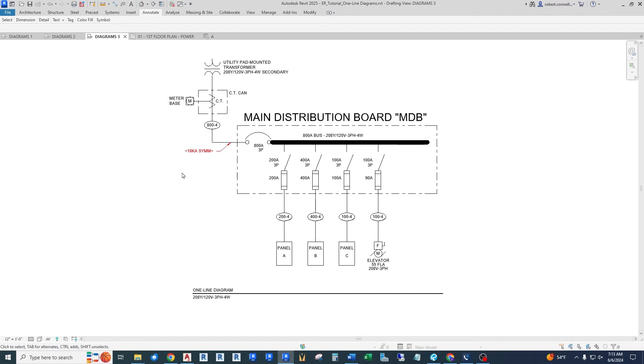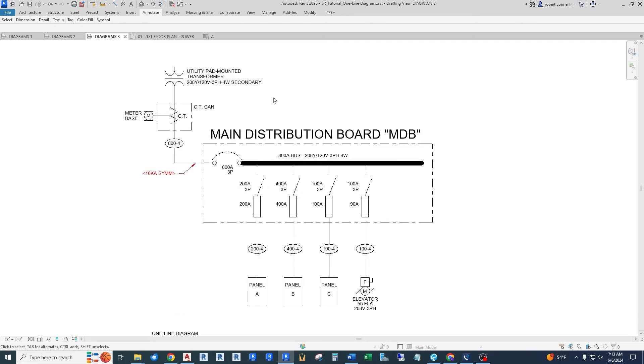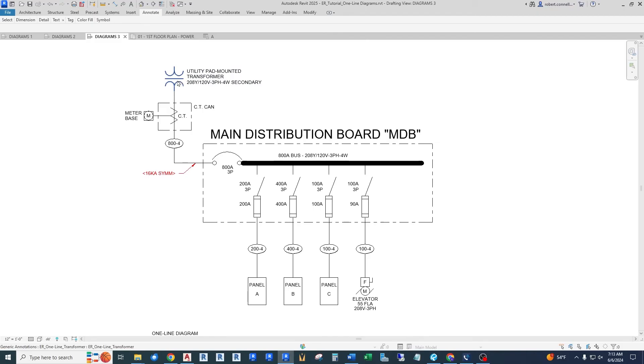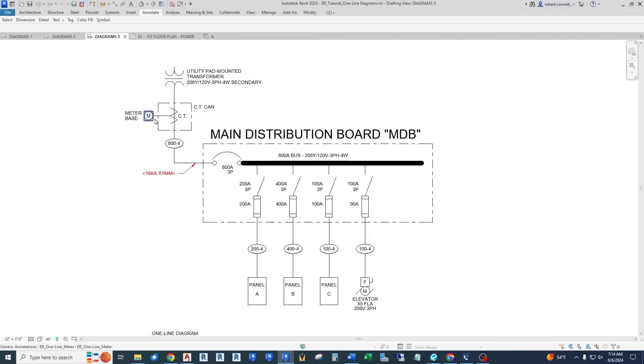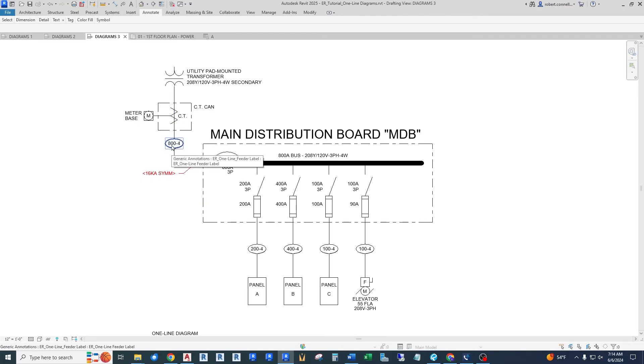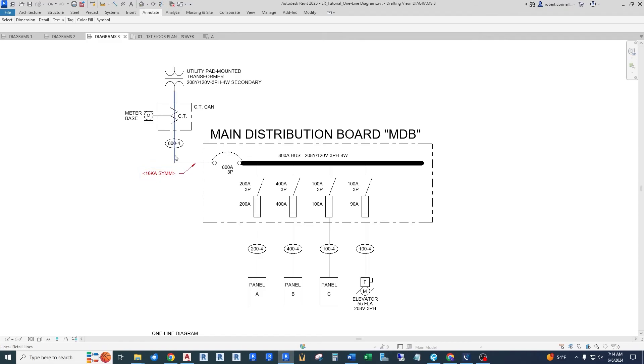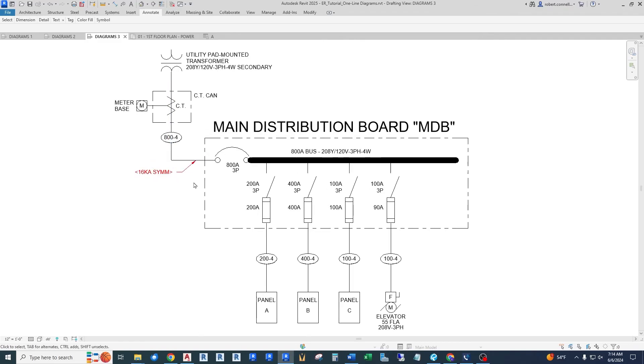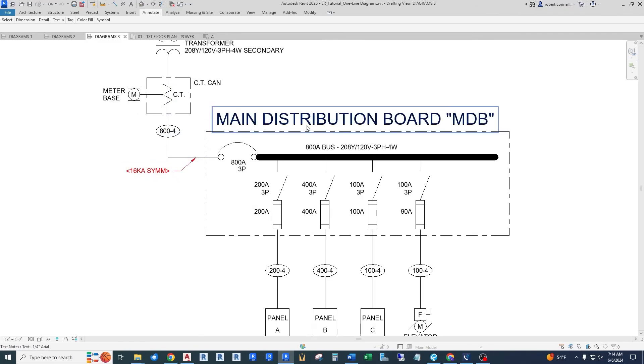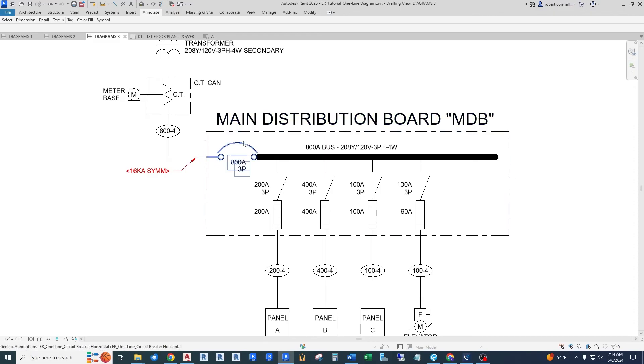So this is a complete building electrical distribution system. Again, we have a source up here, and this ends up being a utility pad mounted transformer, the big green box sitting on a pad. And it feeds into what's called a CT can, a current transformer can that the utility uses to run their meter so they can charge you for your electricity. Comes through the service lateral, which is given a tag, which refers to a feeder schedule. So an 800-4 would represent an 800-amp four wire feeder. And it will tell you what size all those wires are, so I don't have to repeat them over and over on this diagram.